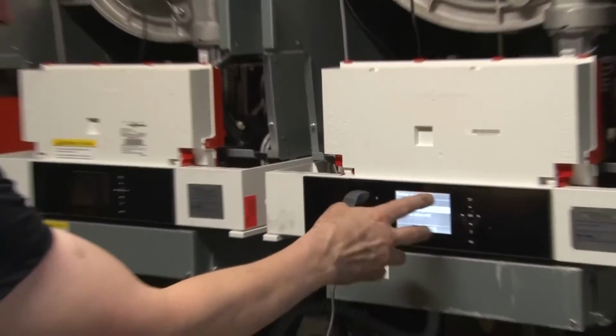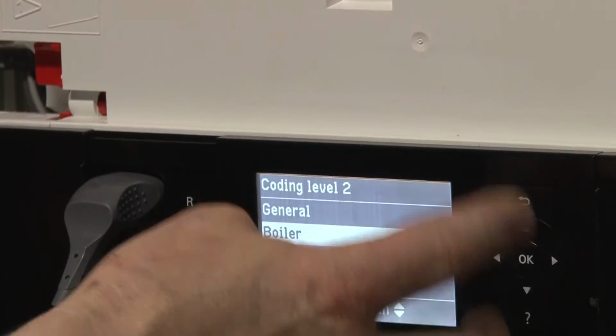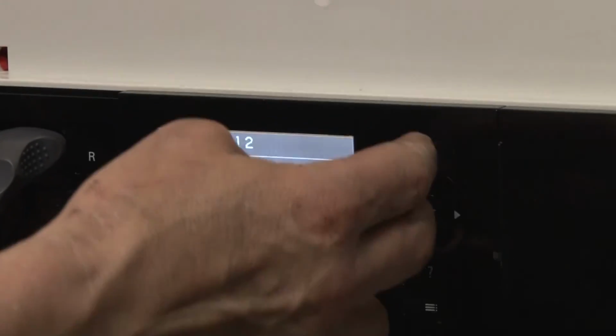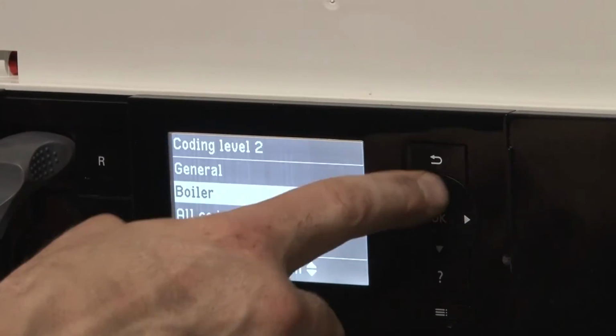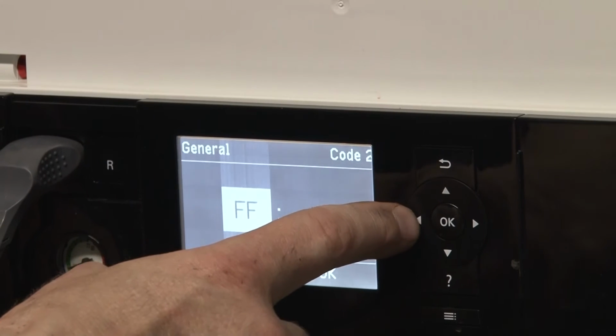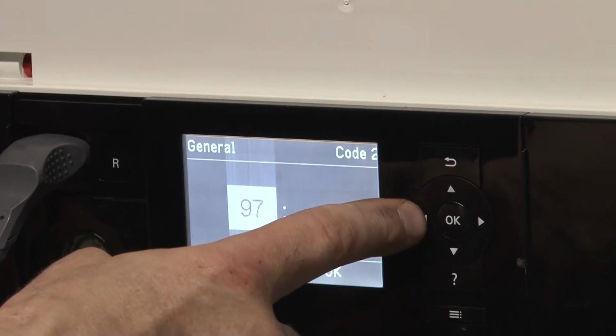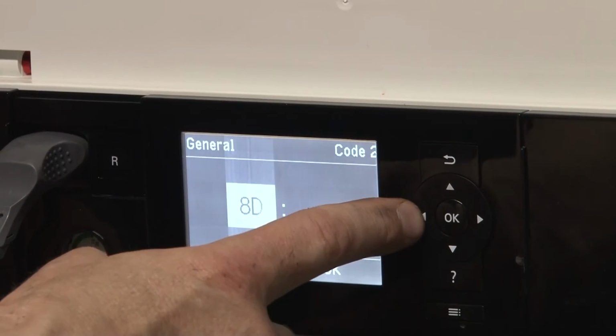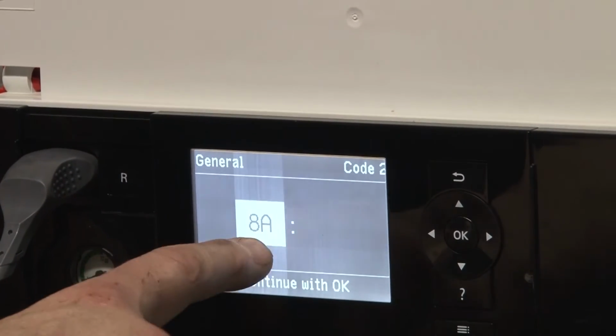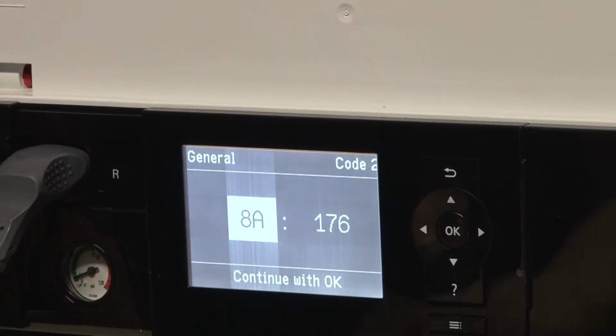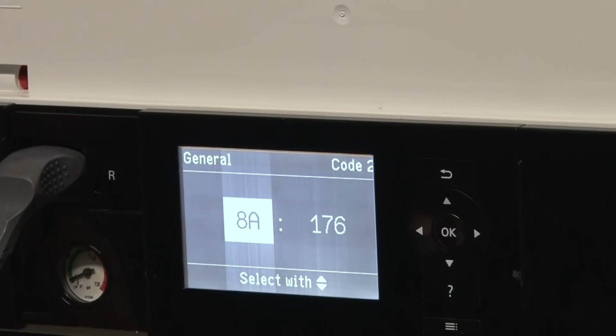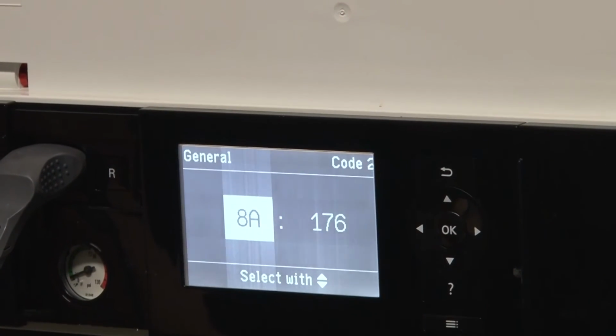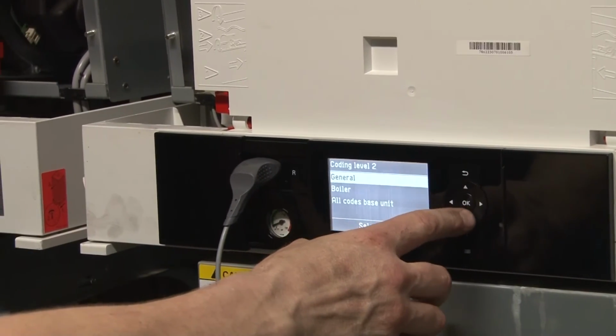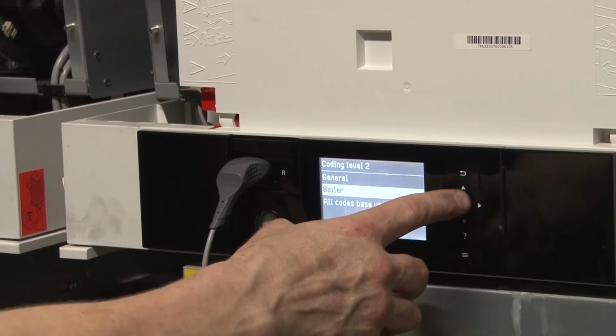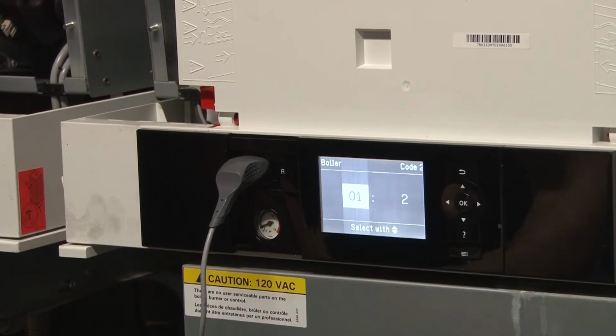What I did there was I went into coding level 2. We already were in the service level, so OK, menu, OK, and the back key gets me to coding level 2. I went to general first, and the idea there was to look at address 8A. 8A is an address that opens up other addresses if it's at 176. Usually it's at 175, and I have to change it to 176. This one had already been at 176. Obviously somebody's already been in this control doing the same thing. Once I get 8A at 176, I scroll down to boiler, push OK, hit the left arrow key once.